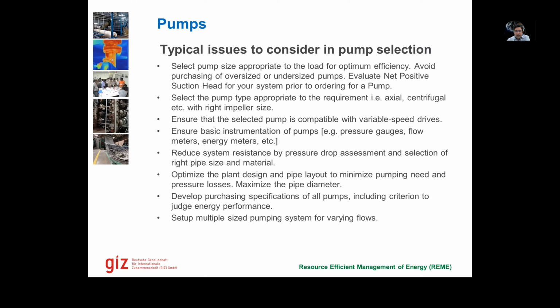Typical issues to consider in pump selection are to select the right size of pump based on the net suction head. The pump type is also very important depending on what kind of requirement we have. Do we want an axial flow or a centrifugal flow pump? And then compatibility with variable speed drives is important. Some pumps are not compatible with VFDs because these are old technology pumps. We often see that pumps do not have type plate readings, so we are not even able to see what the rating of the pump is.